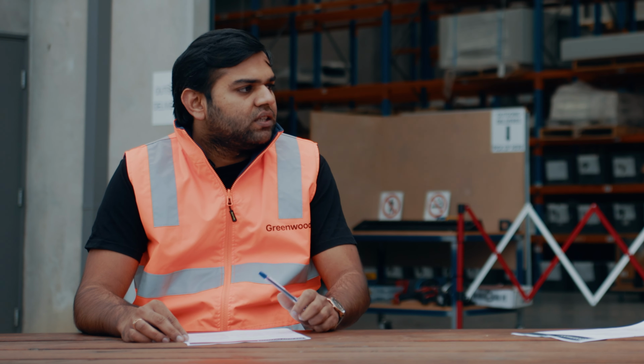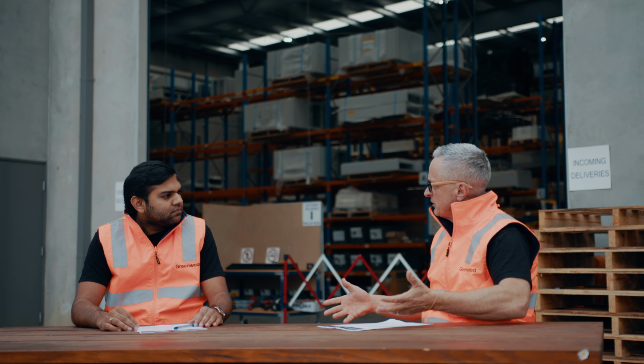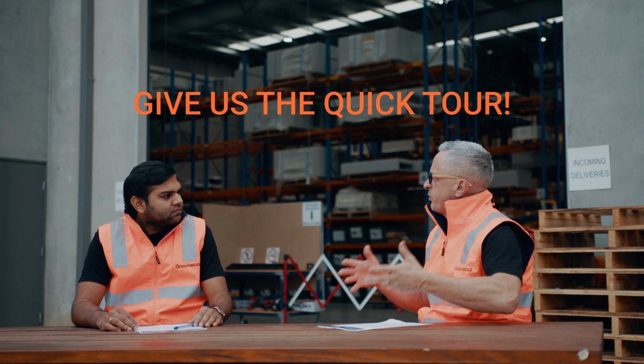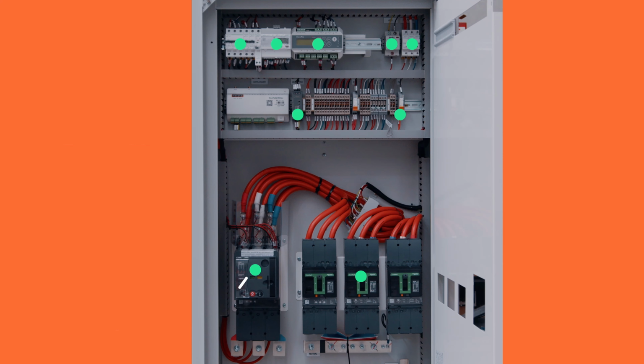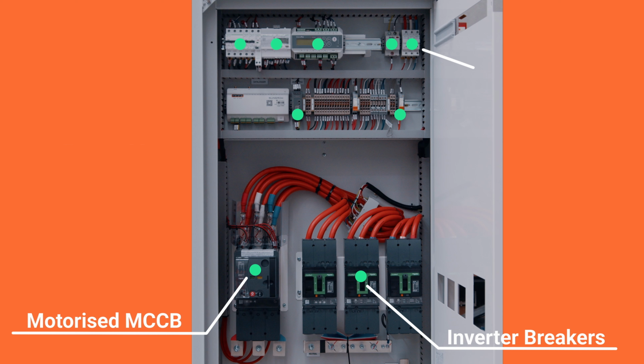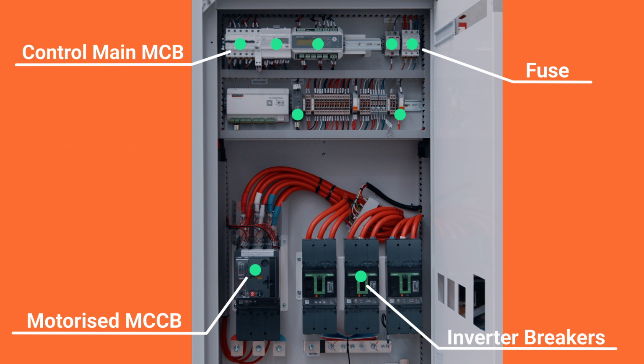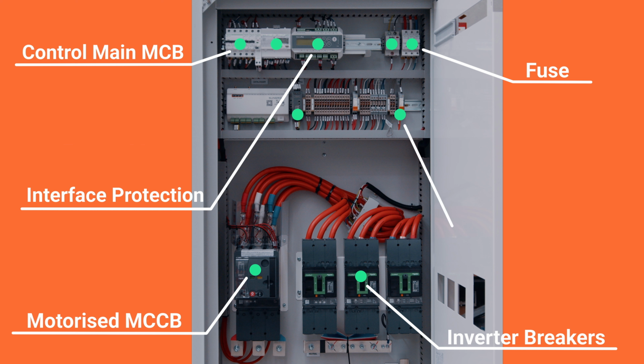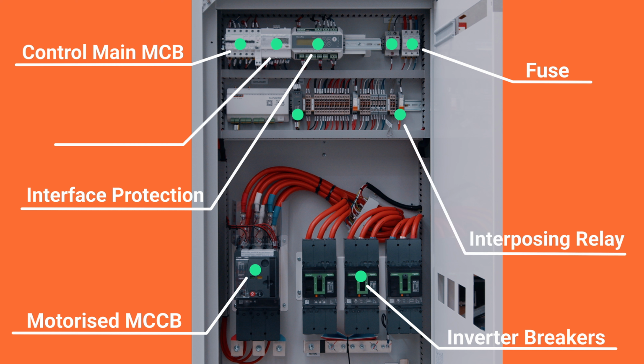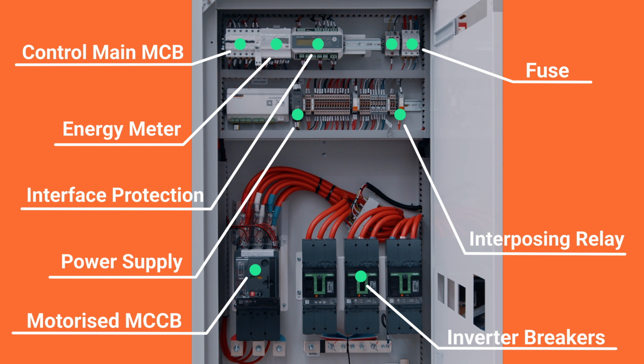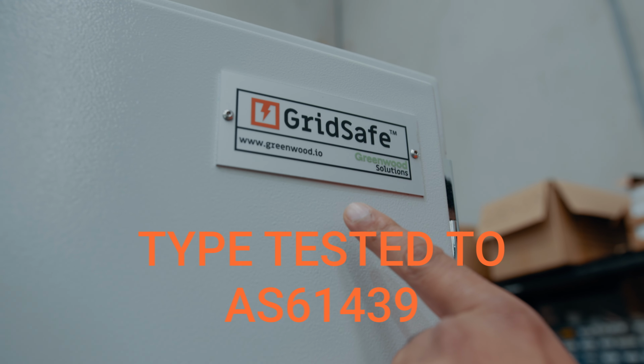Can you give us a quick tour of the manufacturing plant and explain what is pre-wired in our GridSafes? We would have motorized breaker, inverter breakers if required, fuse for the control gear, main switch MCB, secondary protection relay, which is now called interface protection, interposing relay, energy meter, power supply, GPO, etc. Over the most, additionally, it is type tested to AS 61439.